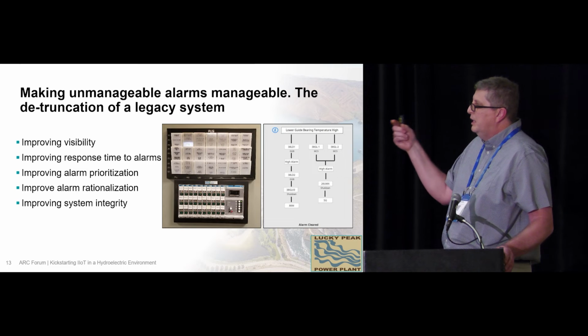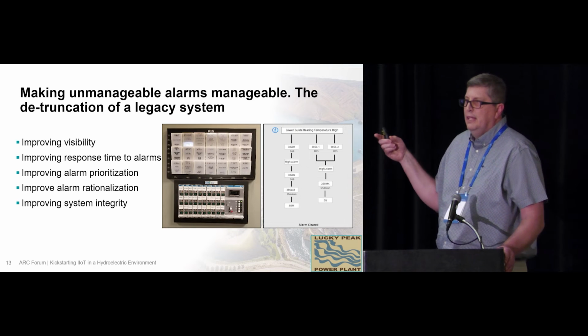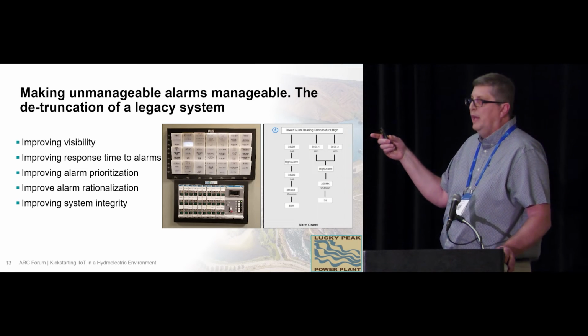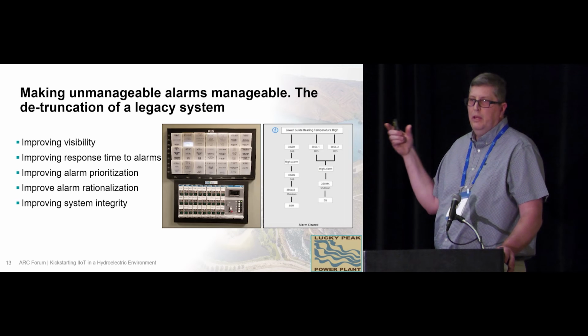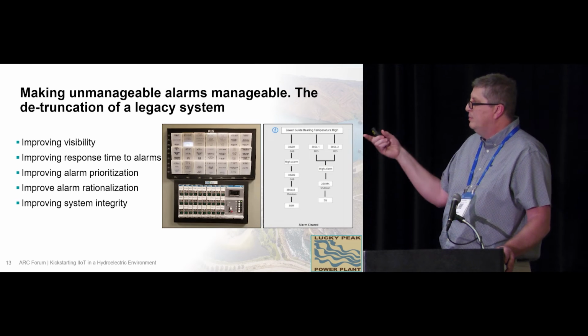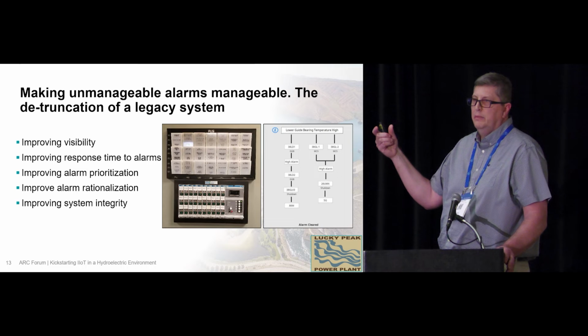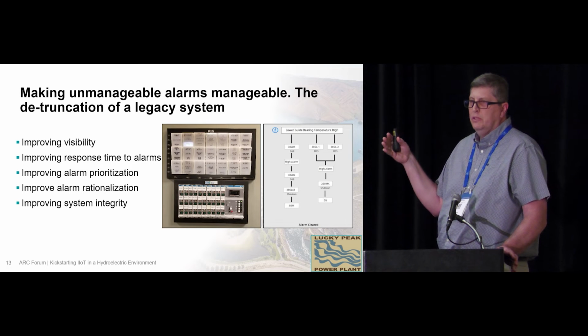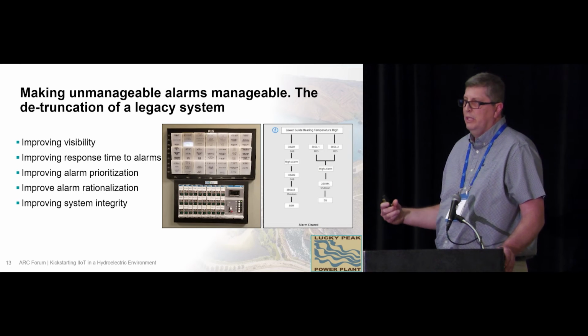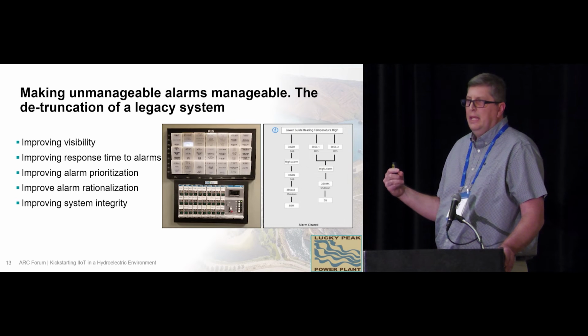As we look at the templates for our devices, we separate them under our systems and bring up a template for that system. When an alarm comes in, the actual device lights up red, letting the operator know exactly which device under that system is active. We also provide a tree, like an electrical schematic, of all the devices below that before it reaches the end device that might shut things down.